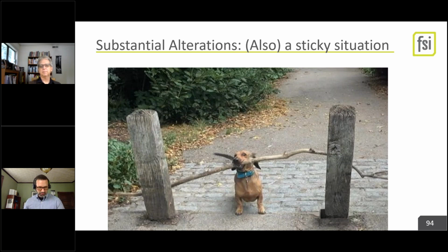I want to reiterate what Duane just said a bit. If you have, in Seattle and possibly in the next version of the Washington Code depending on the next couple months, a gas-based boiler, you will not be putting in a gas-based boiler again unless it's an emergency, like honest to goodness emergency - a planned replacement won't count for that. So think 180-degree hot water up to steam, up to hotter than that. We have trouble with heat pumps getting there right now. So if you have an old boiler system that wasn't designed to be condensing and at lower temperatures, you're going to have a more major system upgrade than just that boiler. You're going to have to at least address coils out in heat rejection equipment, wherever that is putting its heat out to - air handlers, radiators, whatever it is. We can't make steam with heat pumps right now.